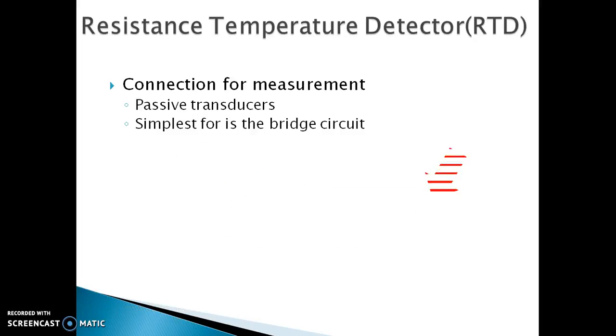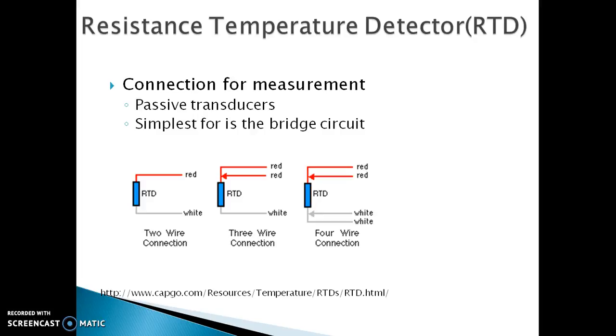RTDs are resistive devices, so the lead resistance directly affects the accuracy. The error can be quite large and hence, we have these three connections which are available.